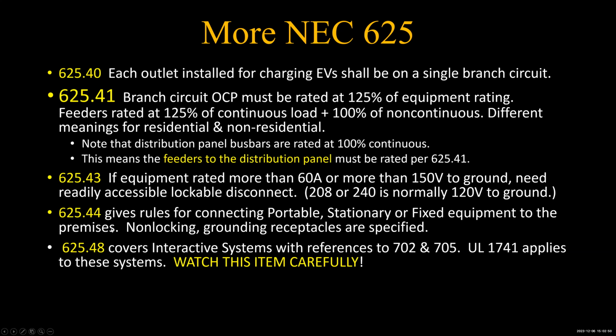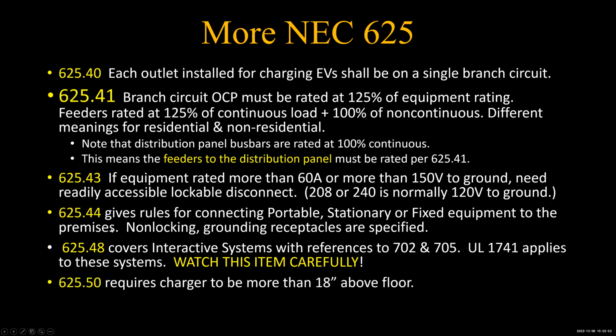All right, so watch that 625.48. We're going to see some action on that in the next couple of years. And of course, if you're in the garage, the outlet has to be more than 18 inches above the floor, not because of the electric vehicle, but in case you've got a gasoline vehicle parked alongside of it. All that heavy gasoline vapor settles to the floor, so the electrical has to be more than 18 inches above the floor. And those electrons don't stay close to the floor. They pretty much stay in the batteries.